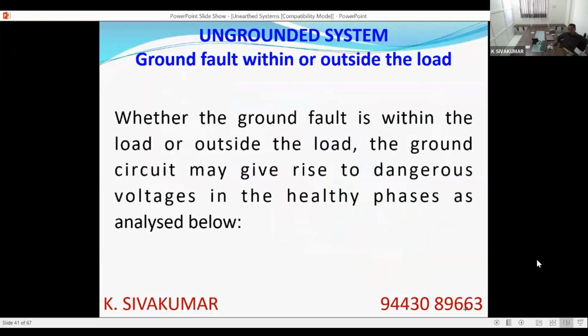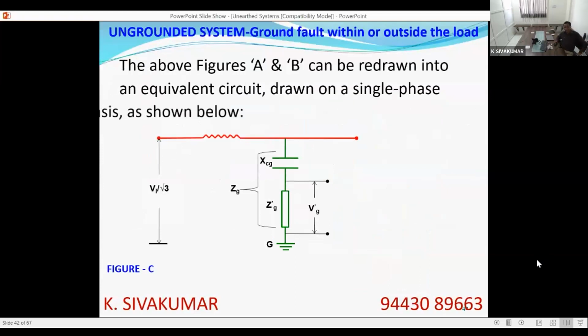So now, as you have seen in the above two diagrams, whether the fault is within the equipment or outside the equipment, there will be added impedance in the earthing circuit. If you draw the equivalent circuit of the added impedance, you can see the voltage to earth is VL by root 3. There is a network impedance, there is resistance, and ZG is the new impedance introduced into the ground circuit by the fault. XCG is the ground capacitance. It may be XC R, XC Y or XC B. So you can see this ZG is the total impedance, the sum of Z dash G plus XCG. Z dash G is the additional impedance introduced in the ground circuit during fault conditions. V dash G is the voltage developed across the external impedance.